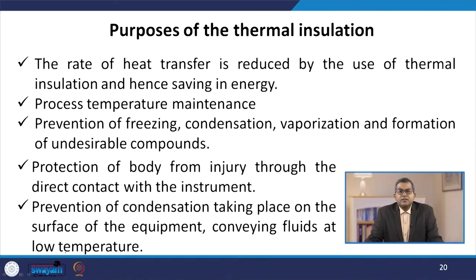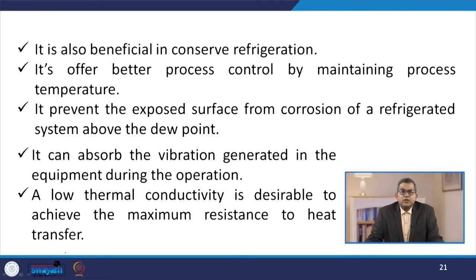Now let us talk about the purpose of thermal insulation. The rate of heat transfer is reduced by the use of thermal insulation, hence saving energy — this is the foremost requirement. It helps maintain process temperatures, prevent freezing, condensation, vaporization, and formation of undesirable compounds. It provides protection from injury through direct contact with equipment. It prevents condensation on surfaces conveying fluids at very low temperatures, conserves refrigeration, offers better process control by maintaining process temperature, prevents corrosion of a refrigerated system above the dew point, and can absorb vibration generated in equipment during operation. A low thermal conductivity is desirable to achieve maximum resistance to heat transfer.